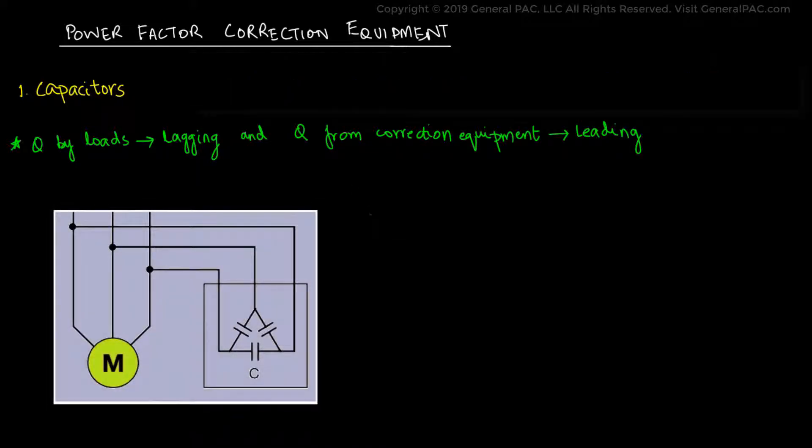First up, we have the static capacitor, which are the simplest form of power factor correction still in use today. This method consists of inserting a capacitor bank in parallel with the incoming terminals of the inductive load. Once inserted, the reactive power by the inductive load is supplied by the capacitor bank, which neutralizes the effect and improves the power factor magnitude.